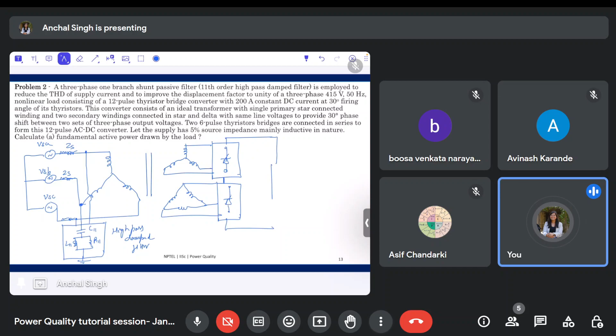Why are they connected in star and delta fashion? In order to provide a 30-degree phase shift. And why do we need that? Because we are using two 6 pulse converters to form a 12 pulse converter. By connecting these two 6 pulse converters, phase shifted by 30 degrees, we obtain a 12 pulse converter, and this is my load which requires the output of a 12 pulse converter.